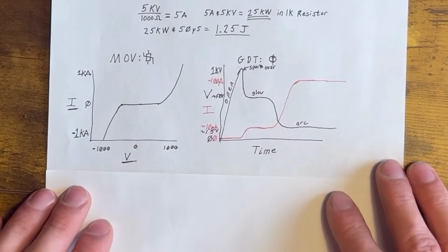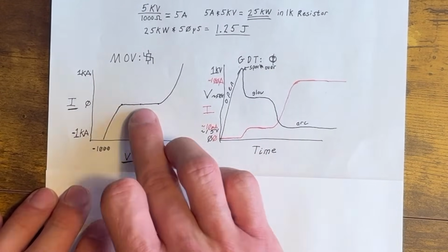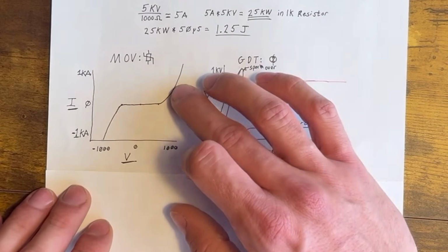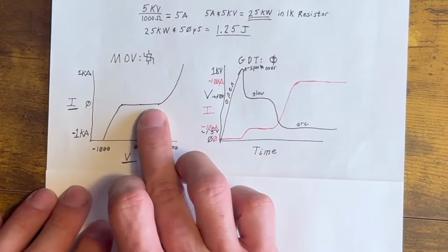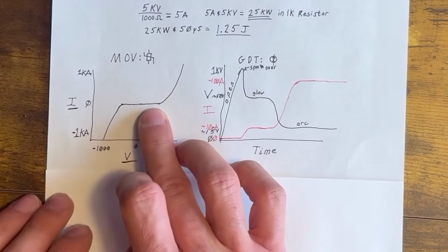The second you drop the voltage below that point, it turns right back off as well. So if you bring a 1,000 volt MOV up to 1,500 volts, it'll conduct like 1,000 amps. And if you drop it back down to 800 volts, it'll turn back off instantly.